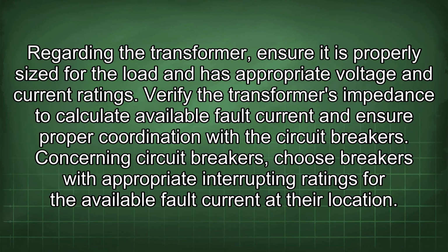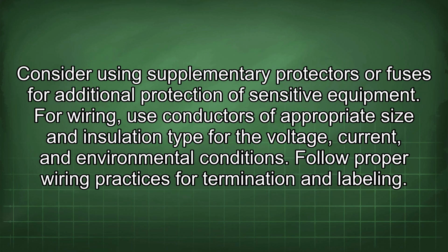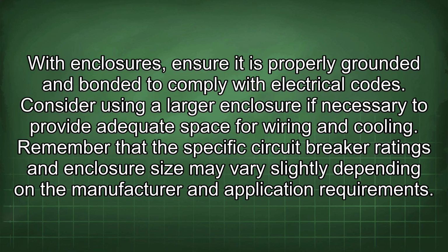Concerning circuit breakers, choose breakers with appropriate interrupting ratings for the available fault current at their location. Consider using supplementary protectors or fuses for additional protection of sensitive equipment. For wiring, use conductors of appropriate size and insulation type for the voltage, current, and environmental conditions. Follow proper wiring practices for termination and labeling. With enclosures, ensure it is properly grounded and bonded to comply with electrical codes.